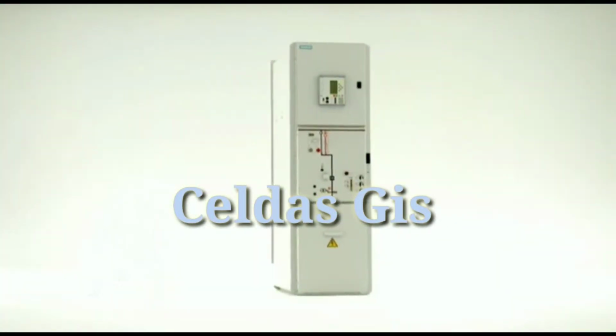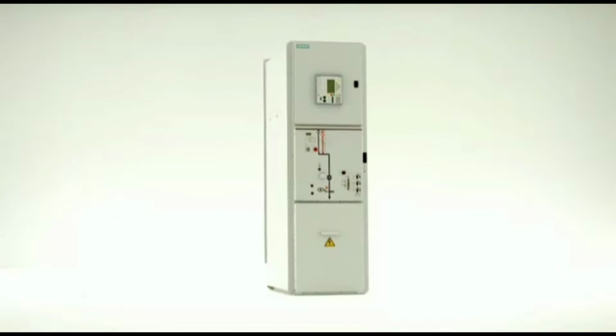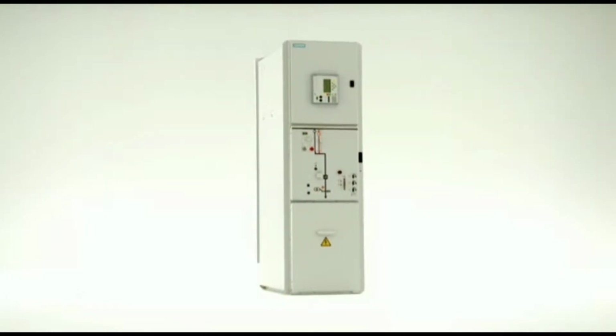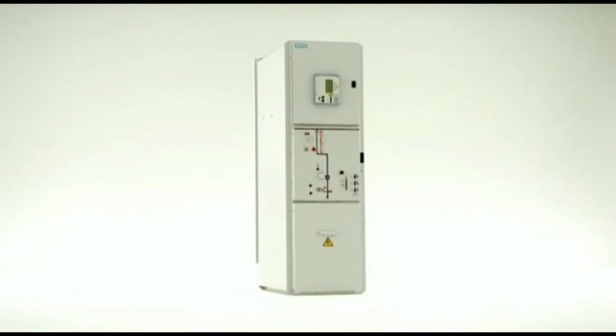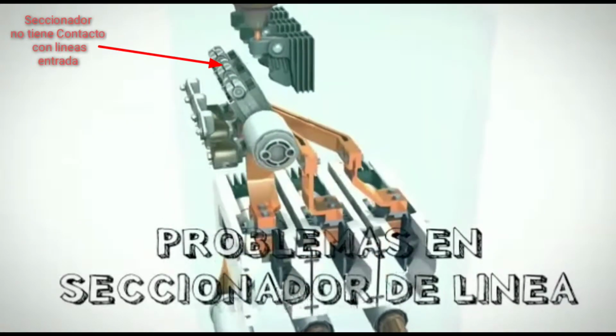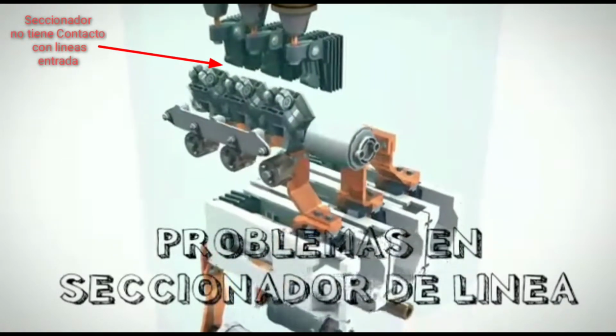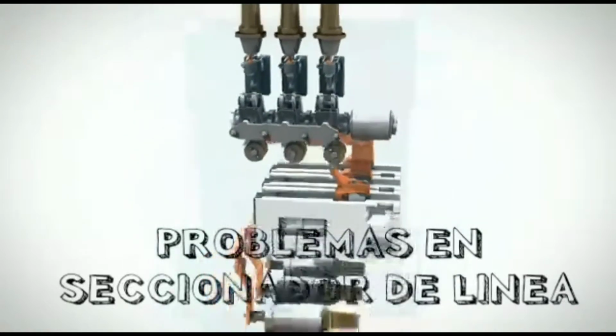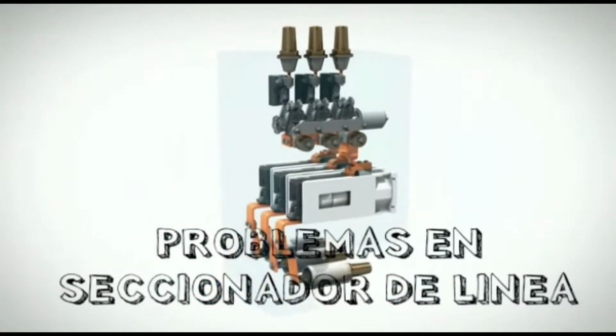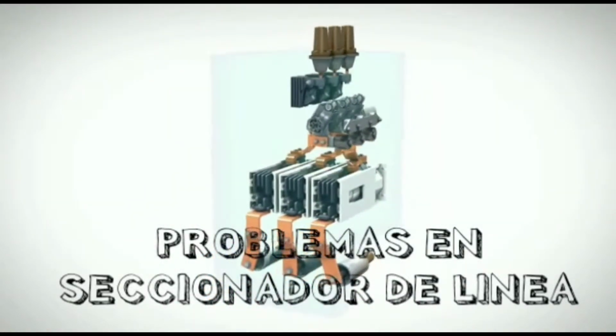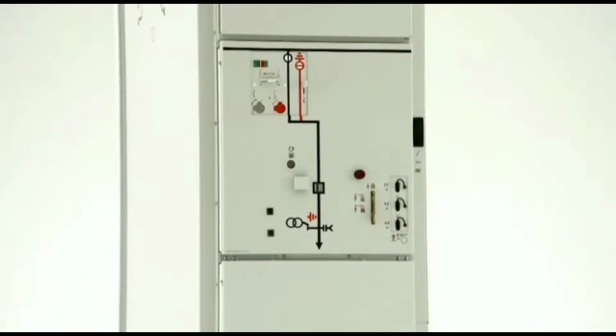Circuit breaker switchgear by Siemens is installed in the primary distribution level by customers from the power utility and industrial sector. Combined with the vacuum switching technology of the circuit breaker, the gas insulation of these switchgear assemblies provides a high level of security of operation and personal safety. Here, the choose and execute principle ensures faultless operating sequences.